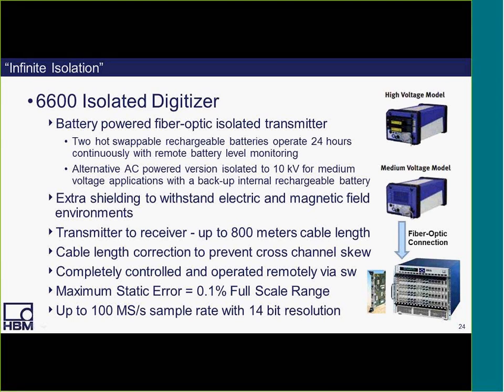In fact, there may be several points throughout your lab that are of a different distance, so even the cable length correction is done automatically to prevent cross-channel skew. Now, it's completely controlled and operated remotely via software, and the maximum static error is 0.1% of full-scale range. And you can achieve up to 100 million samples per second on every channel with 14 bits of resolution.